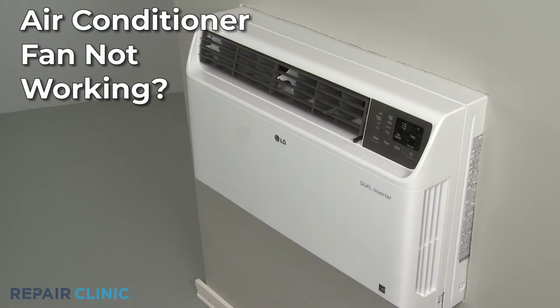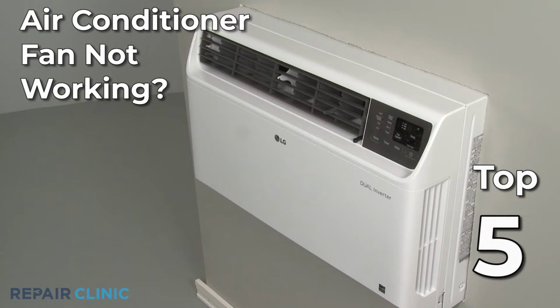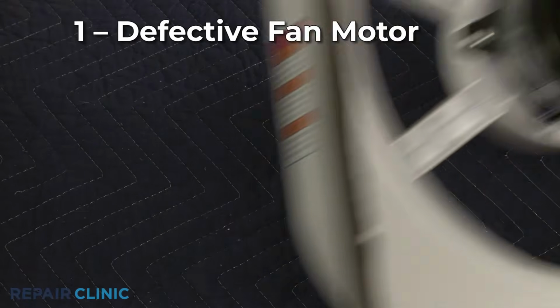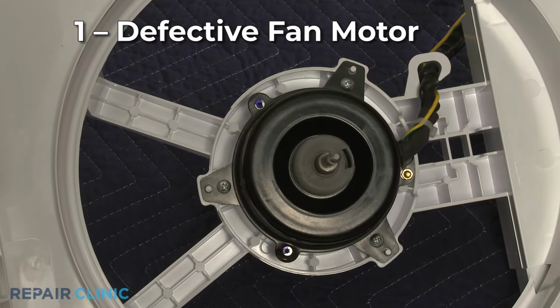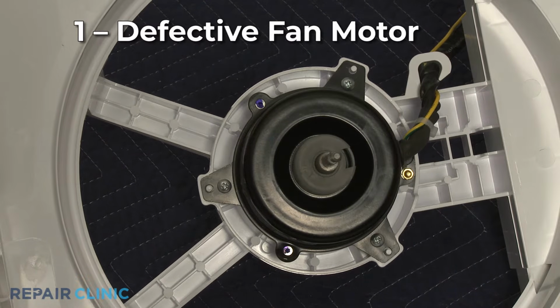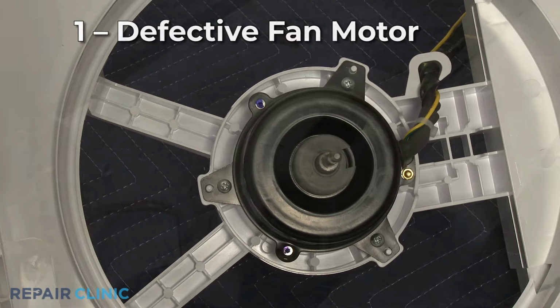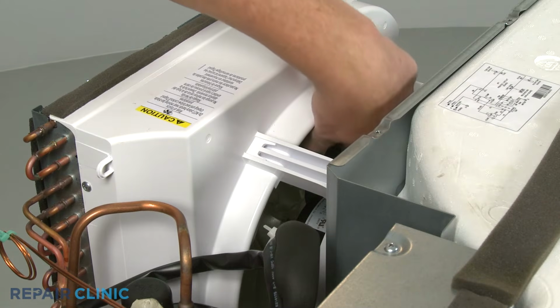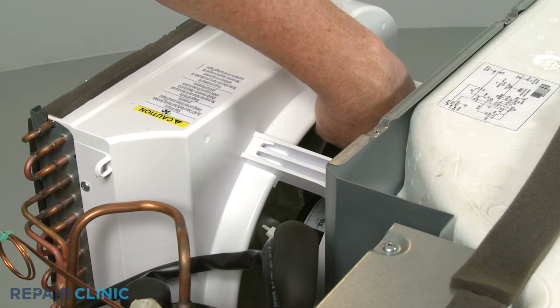If your air conditioner fan is not working, here are the 5 most probable causes. The fan motor may be defective and unable to draw air into the AC unit or force it back out through the front vents. Try turning the fan blade or blower wheel by hand.